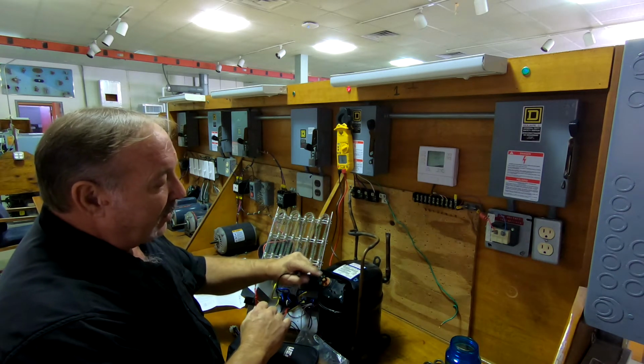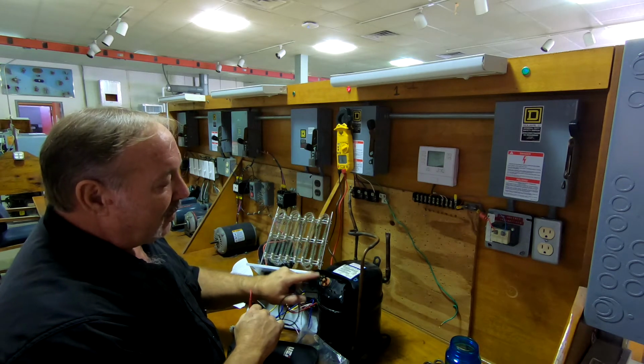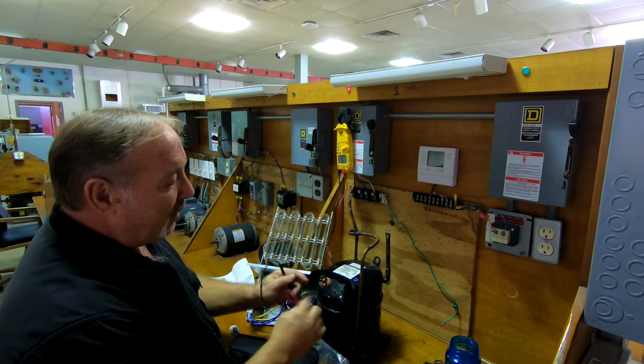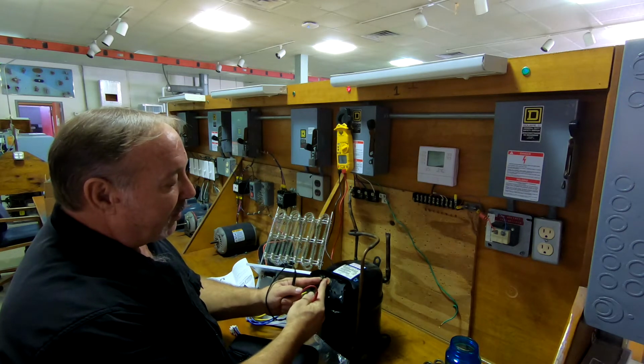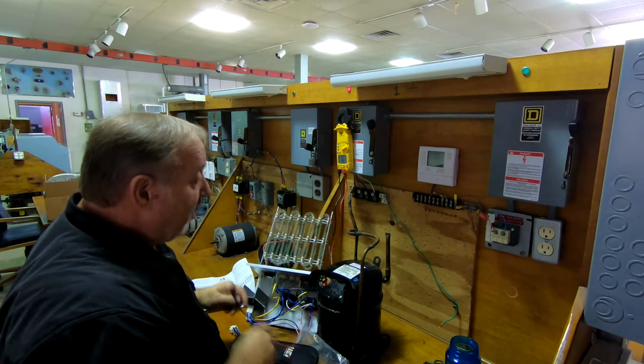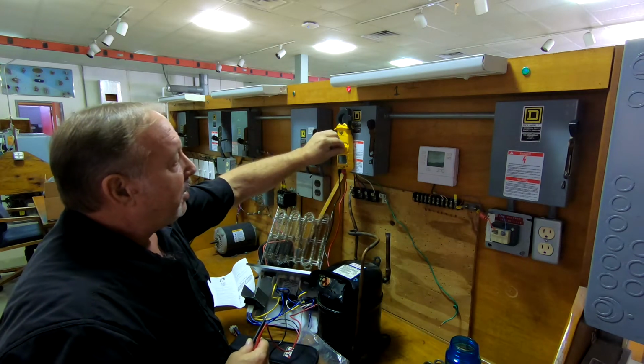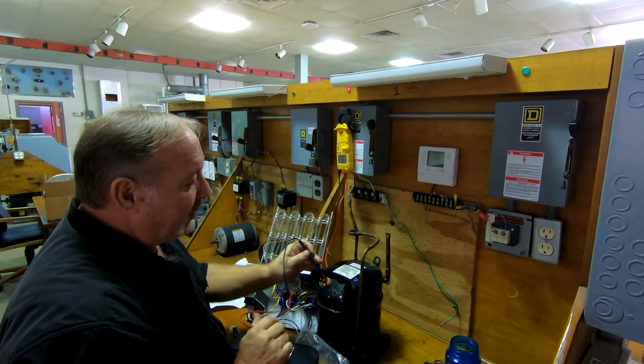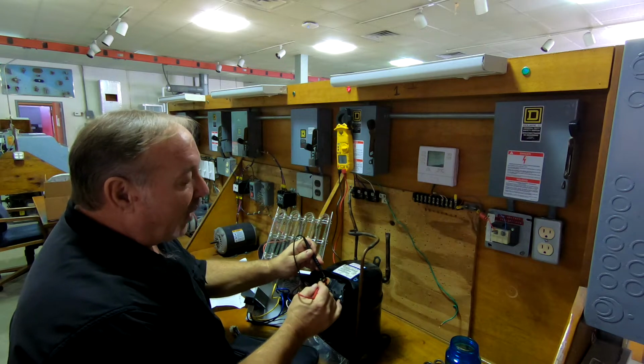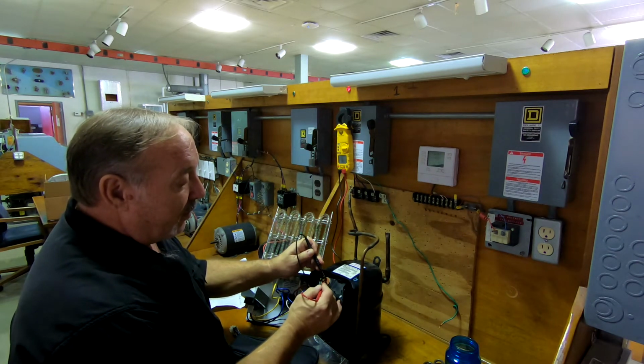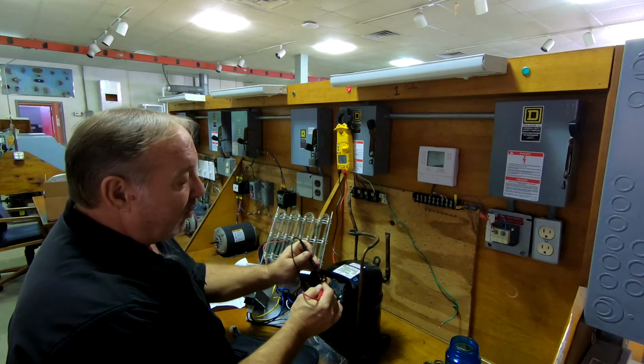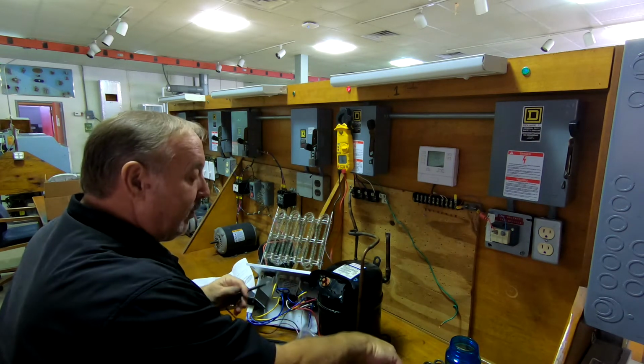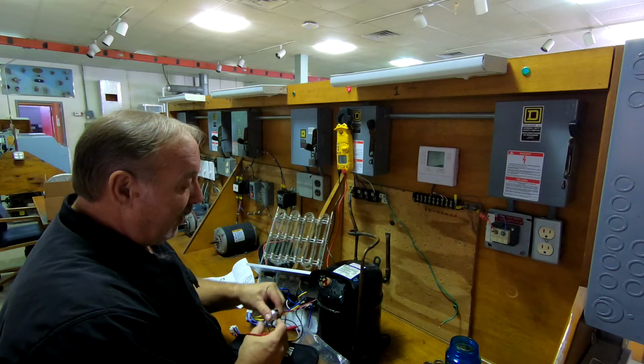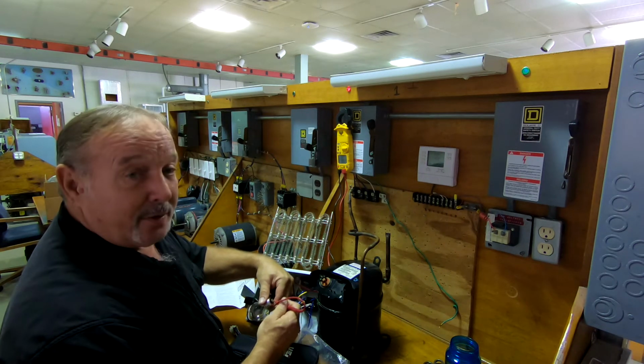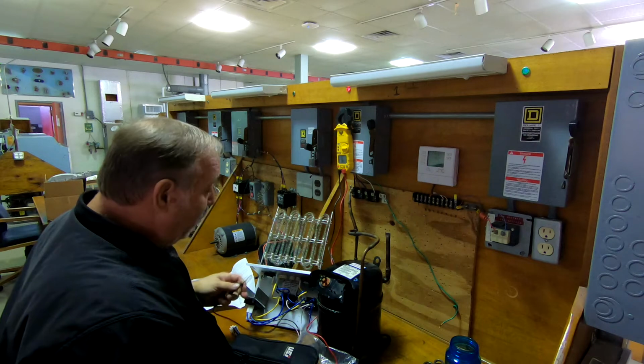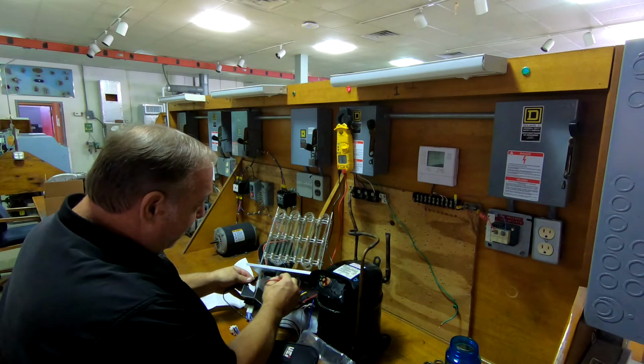So the sum of these two terminals, from common to start and common to run, are additive when you go across the start and run windings. Okay, the other thing we can do is check for continuity. That just tells you if the wiring is good between the terminals. Simple check. We can do the same thing with a light bulb to see if the filament is connected to the base properly. We can also do the same thing with a heating coil.